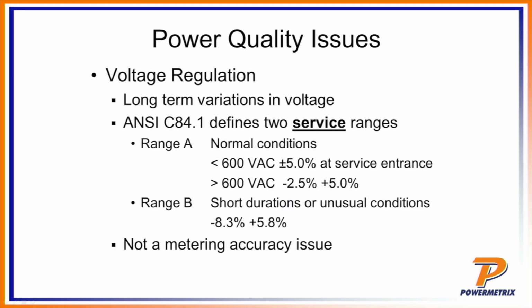I mentioned earlier voltage regulation. Once again, we're talking about long-term variations in voltage over the course of seconds, minutes, hours. ANSI C84.1 defines the deviation that can happen from nominal for both a service range and a utility range. A service range is basically looking at the service entrance, so that would be where the meter is being hooked up to the system. Range A is normal conditions, and it has two definitions: for less than 600 volt systems or greater than 600 volts. So for less than 600 volts, you have a plus or minus 5% deviation at the service entrance. So you can have a little bit above that or a little bit below that.